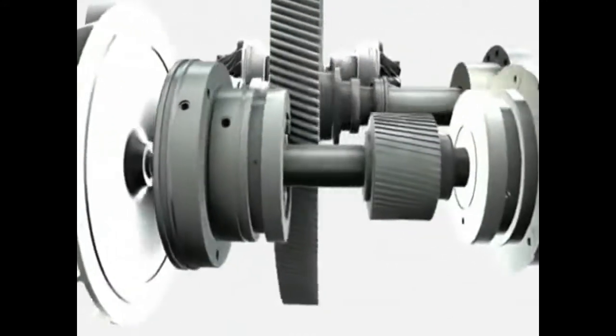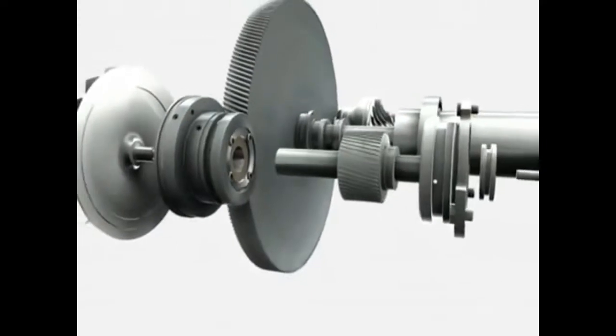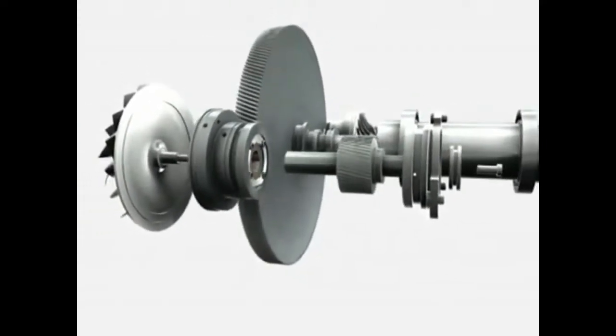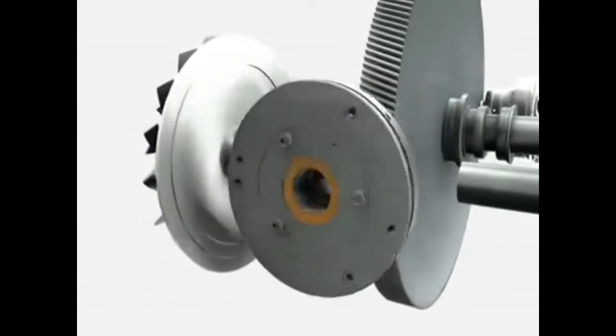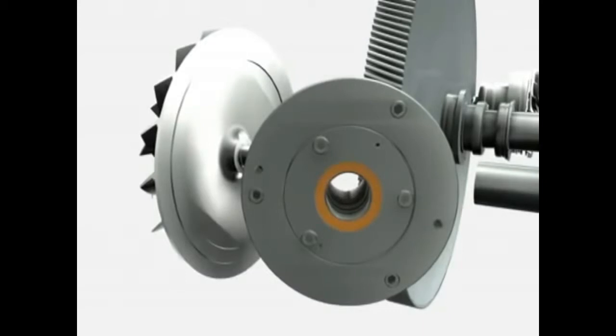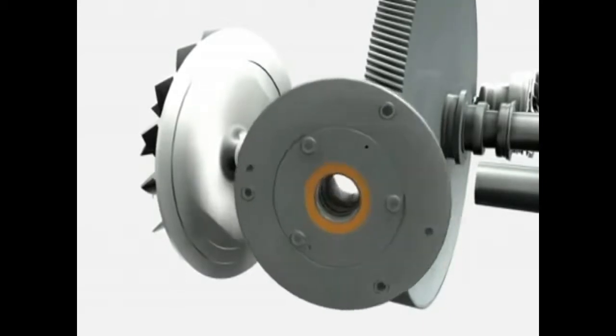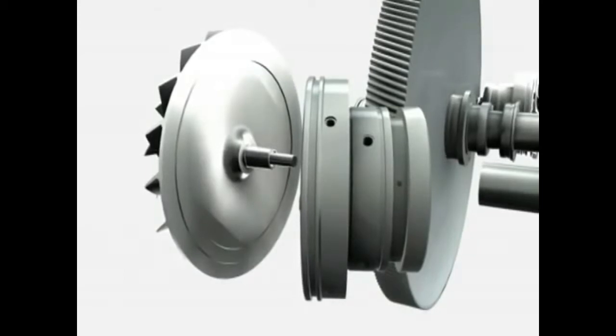The assembly rides on a thin film of oil separated from the air by non-wearing carbon ring seals, ensuring 100% oil-free ISO Class 0 air in all operating conditions, including being unloaded. Single-piece carbon ring seals minimize air loss by more than 50% when compared to labyrinth-style seals, which could save users more than 140,000 kilowatt-hours of electricity per year.